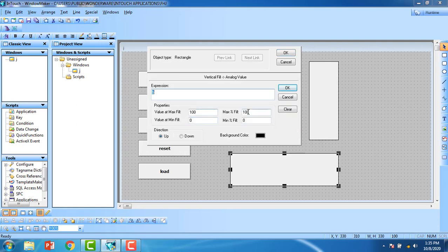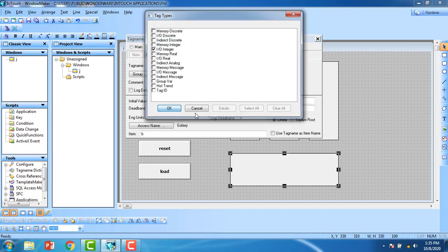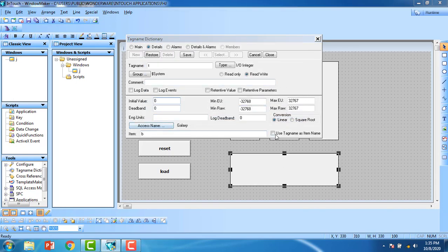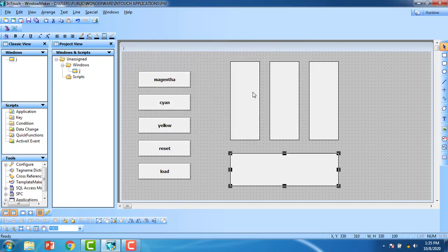These are my three tag configurations. For the total tank fill, define tag 't'. Set the maximum fill to 100 — actually 300 because it is a big tank — and set the expression to 't' for the total. Define 't' as I/O Integer, access name Galaxy, use tag name as item name, save and close.